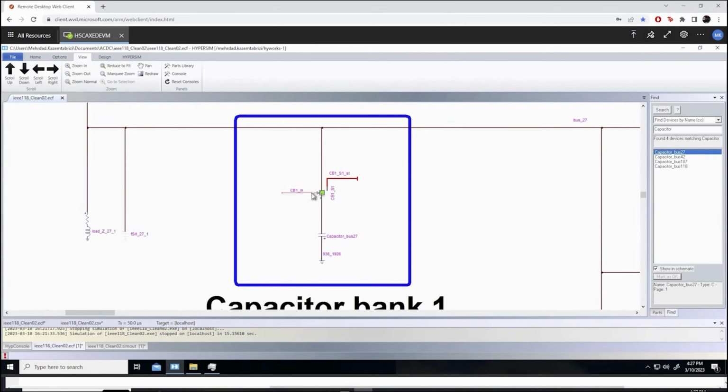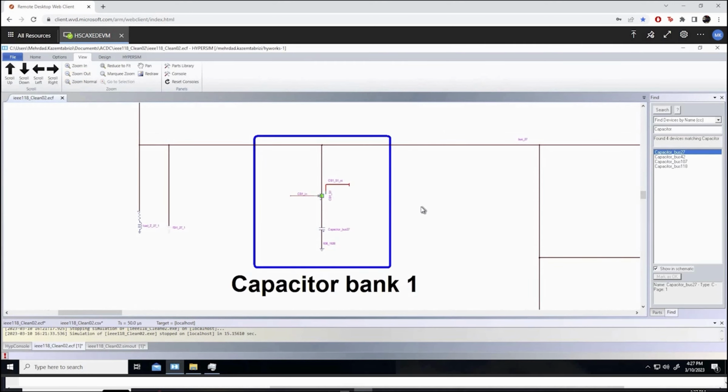The signal to control the breaker, to close it and switch on the capacitor bank to the rest of the network, is coming from the controller. The communication protocol for this signal is Modbus TCP, and it's coming directly from the model that is running on the controller side. So if a fault occurs and our wide area control algorithm works as intended, there's an undervoltage and the capacitor bank will be switched on by closure of the breaker, and so it will compensate the undervoltage and rectify it.